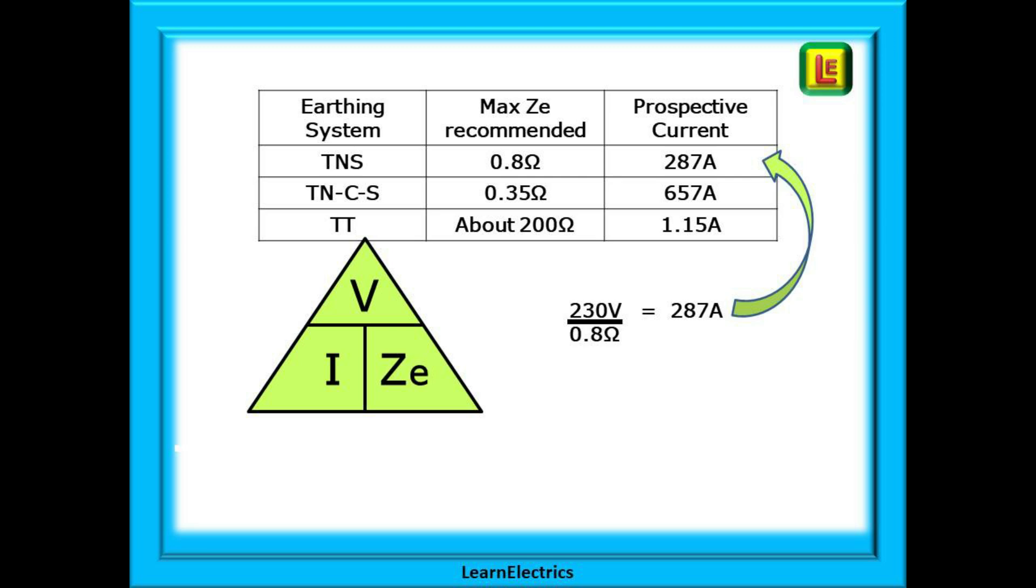Each earthing system has a maximum recommended impedance for ZE, the outside part of the installation. For a TNS system this is 0.8 ohms. Using the ohms law triangle, 230 volts divided by 0.8 ohms gives us a maximum fault current of 287 amps. For a more modern TNCS system the maximum ZE is just 0.35 ohms. Doing the calculation again, up to 657 amps might flow during a fault on a TNCS system. With the TT system things are very different. A TT system can have a ZE of up to 200 ohms and this will only yield a fault current of 1.15 amps in this case. Of course ZE numbers could be lower in all scenarios but we are quoting here the maximum figures suggested to be within normal expectations.